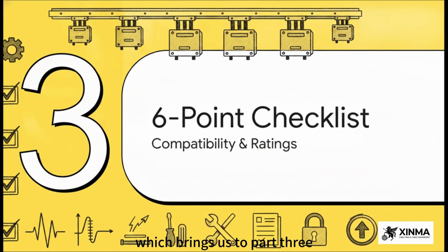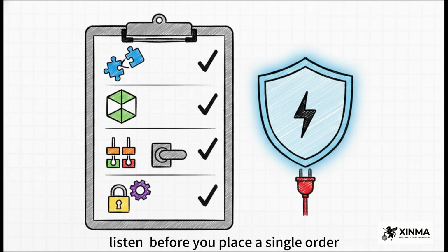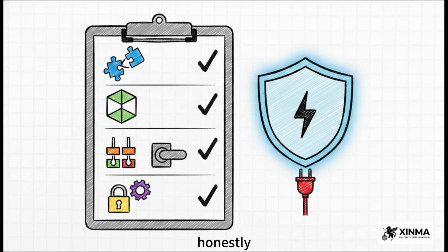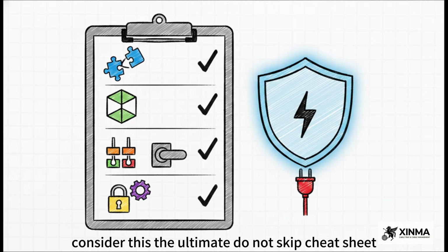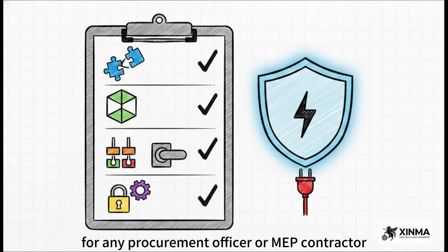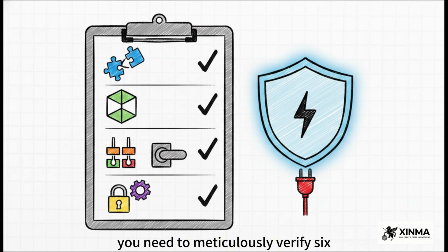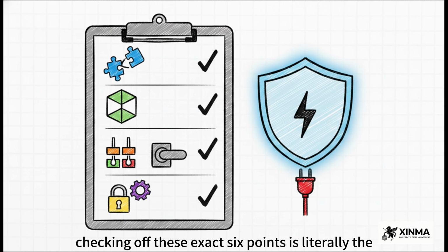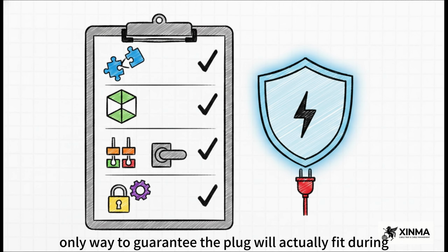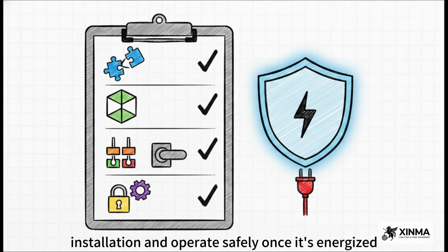Which brings us to Part 3, the 6-element compatibility checklist. Listen, before you place a single order, you absolutely must pass this 6-point compatibility and ratings check. Honestly, consider this the ultimate do-not-skip cheat sheet for any procurement officer or MEP contractor. You need to meticulously verify 6 things: brand and series compatibility, frame geometry, stab arrangement, latch design, interlock mechanisms, and the electrical ratings. Let me be perfectly clear here. Checking off these exact 6 points is literally the only way to guarantee the plug will actually fit during installation and operate safely once it's energized.